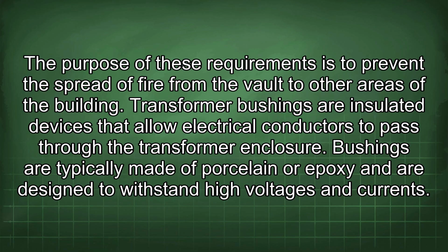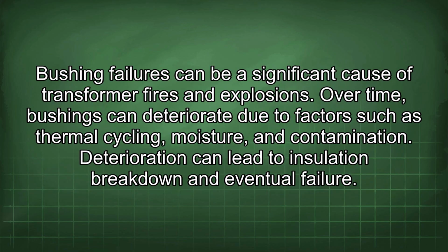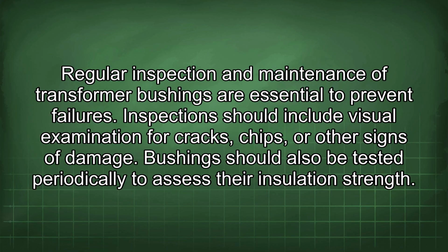the building. Transformer bushings are insulated devices that allow electrical conductors to pass through the transformer enclosure. Bushings are typically made of porcelain or epoxy and are designed to withstand high voltages and currents. Bushing failures can be a significant cause of transformer fires and explosions. Over time, bushings can deteriorate due to factors such as thermal cycling, moisture, and contamination. Deterioration can lead to insulation breakdown and eventual failure. Regular inspection and maintenance of transformer bushings are essential to prevent failures.